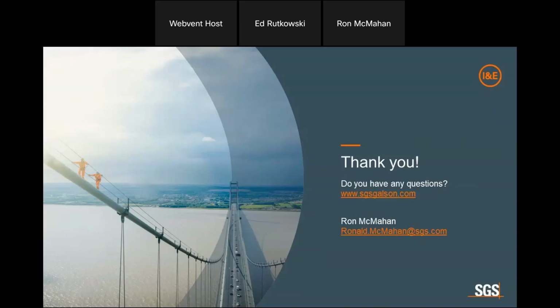I'll tell you, when we first started down the path of this calibration effort, naturally, if you set your reference CO2 level at a concentration, call it 450, and the technicians inadvertently had gotten close to the instrument and interfered with the readings of the SmartSense unit, the unit would read high. So the unit might go to 550, 600. But in the calibration process, they put in 450.